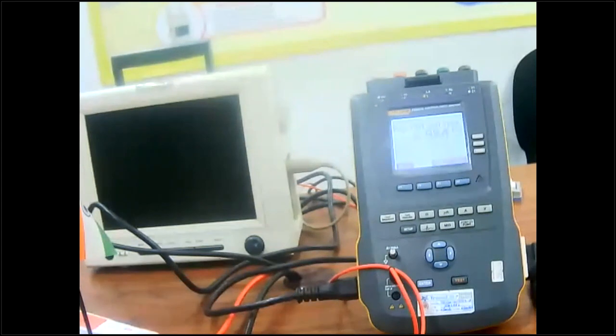Okay. And this touch current leakage test and the way we have just described it is for all medical devices. It's not just patient monitors only, all. So anything where we have no conductive test point, we will use the aluminum foil for the touch current, or formerly called chassis leakage test.